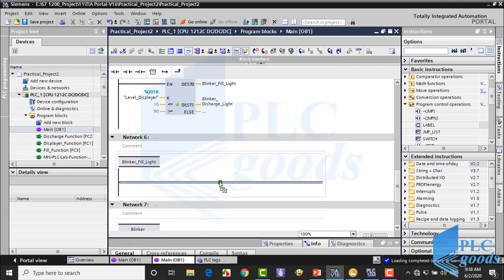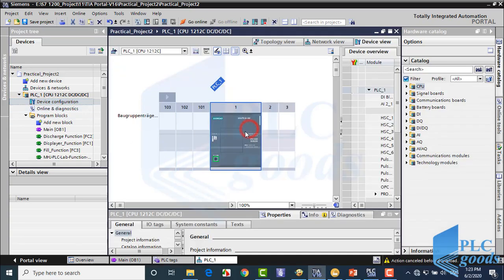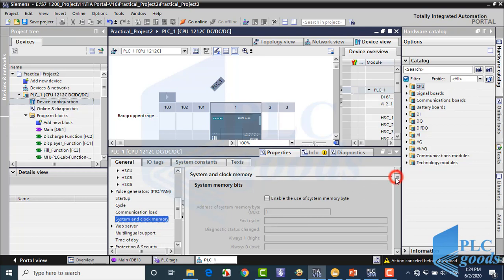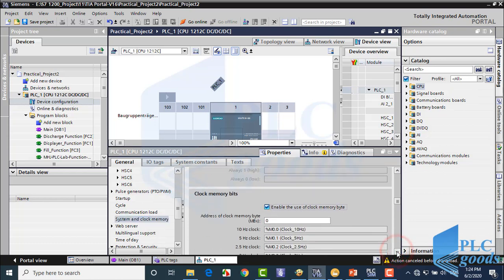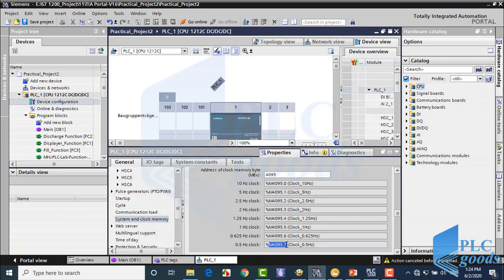At this network with the blinker fill light label, we want to blink the fill light. Here is a simple solution — let me open device configuration, select the PLC, then at the bottom select system and clock memory. Click here to define a memory address as a clock memory byte. For this PLC, we can select a byte number from 0 to 4095. Let me choose the last byte — so every bit of M4095 address will blink with a specified frequency. For example, the last bit, M4095.7, will turn on and off with a frequency of 0.5 Hz. Now let me use this bit to turn on and off the fill light.